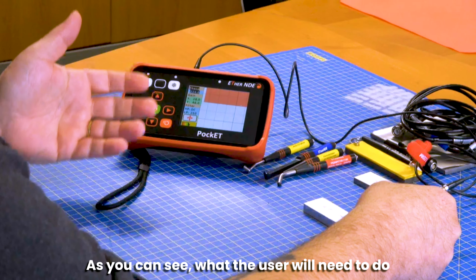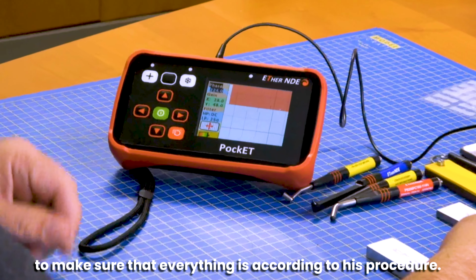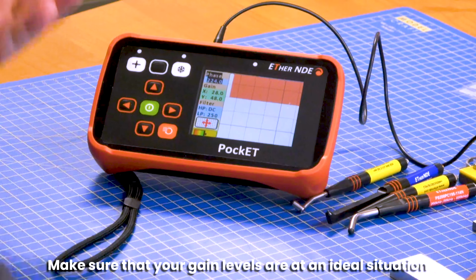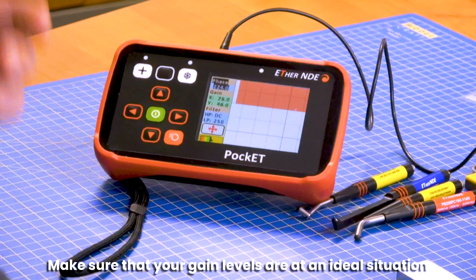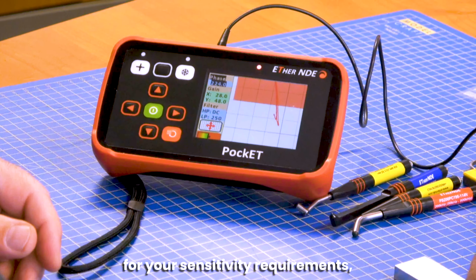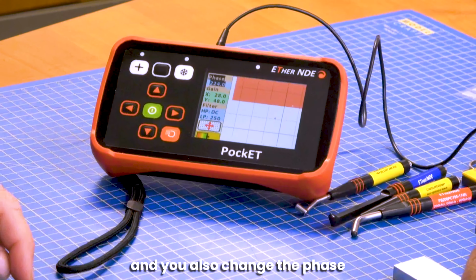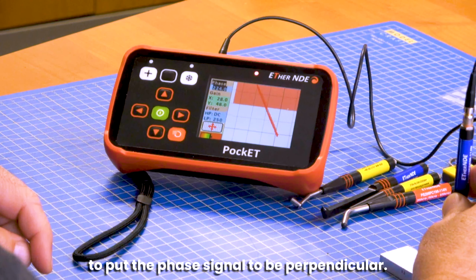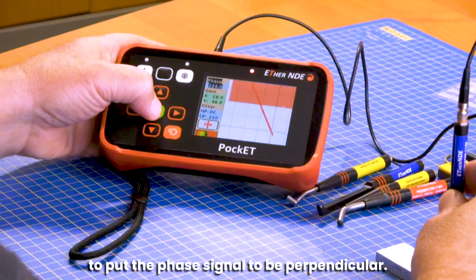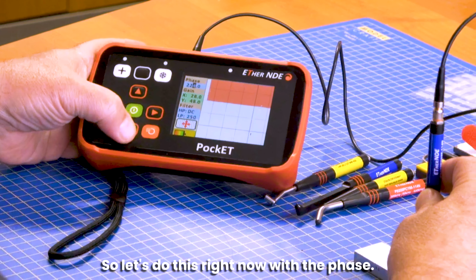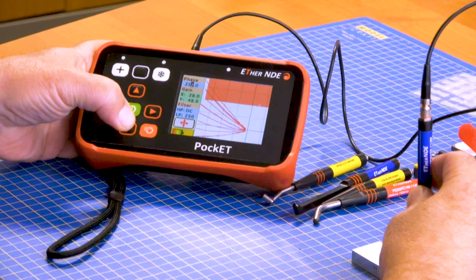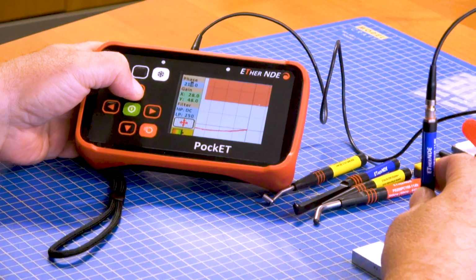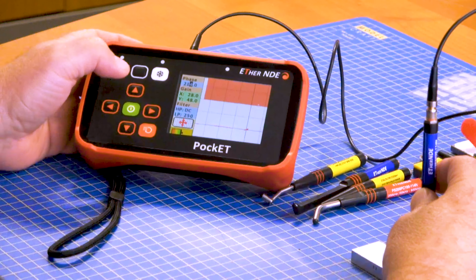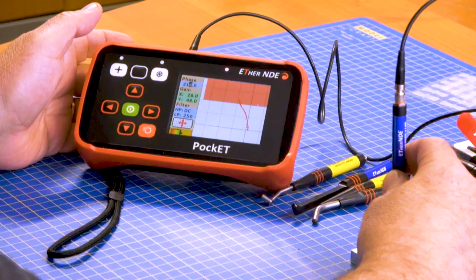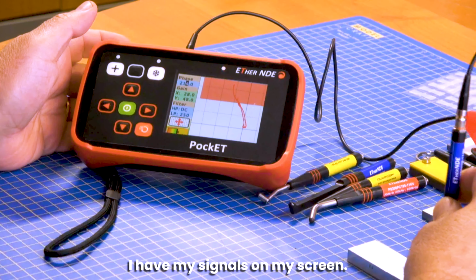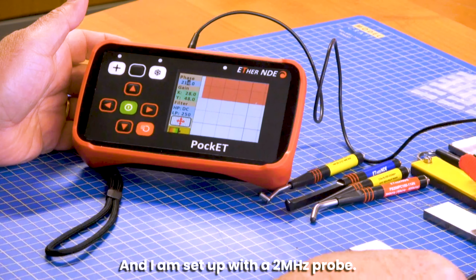what the user will need to do to make sure that everything is according to his procedure, make sure that your gain levels are at an ideal situation for your sensitivity requirements, and you also change the phase to put the phase signal to be perpendicular. So let's do this right now with the phase. A little bit too much. There you go. So now I have my signals on my screen and I am set up with a 2 megahertz probe.